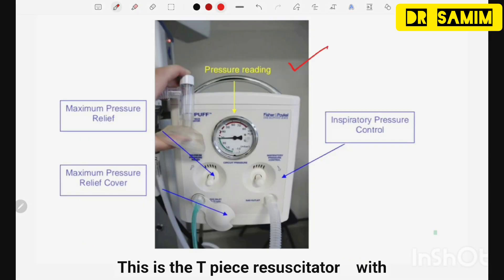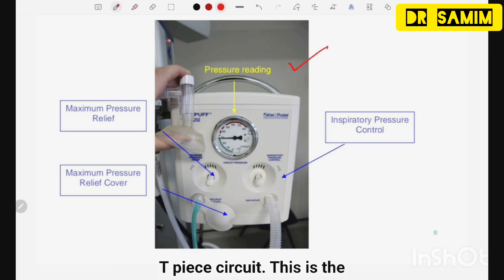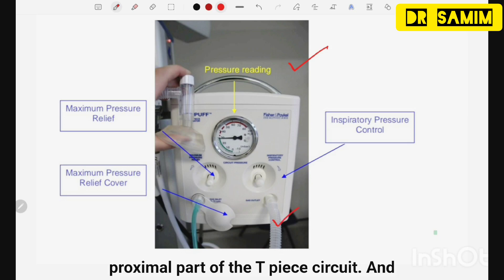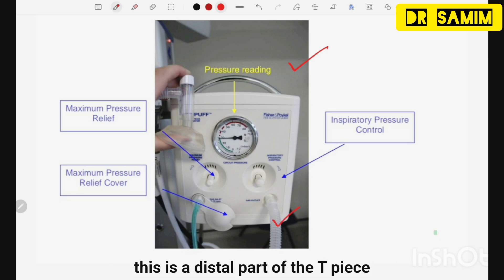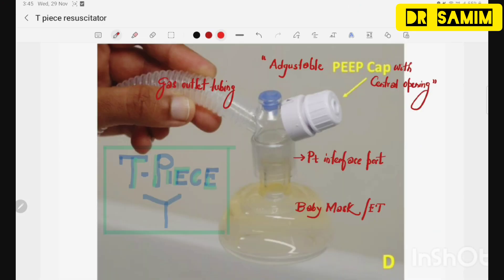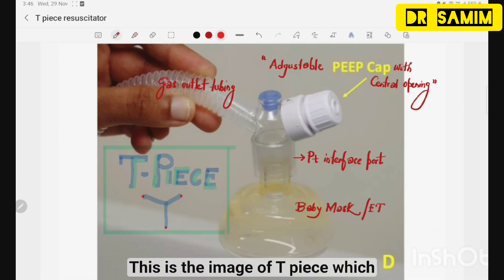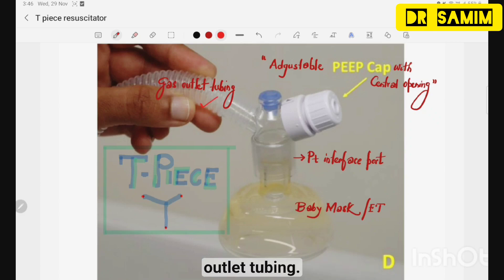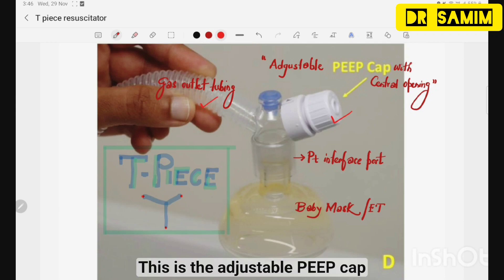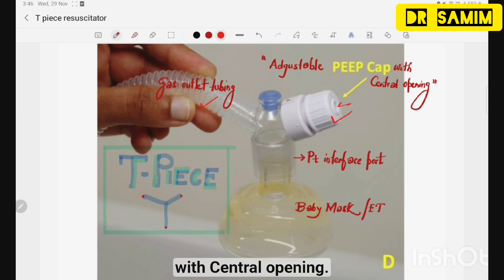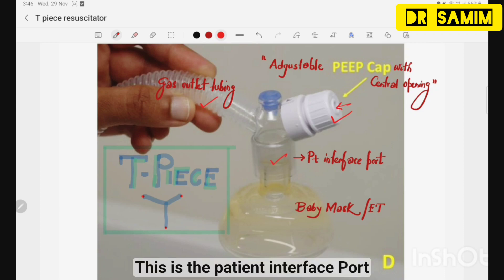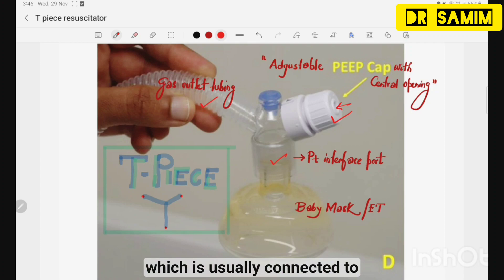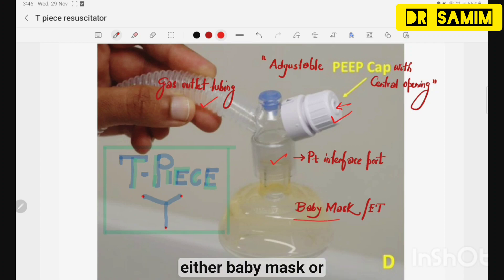This is the T piece resuscitator with the T piece circuit. This is the proximal part of the T piece circuit and this is the distal part. The T piece circuit has three parts: the gas outlet tubing, the adjustable PEEP cap with central opening, and the patient interface port, which is usually connected to either a baby mask or an endotracheal tube.